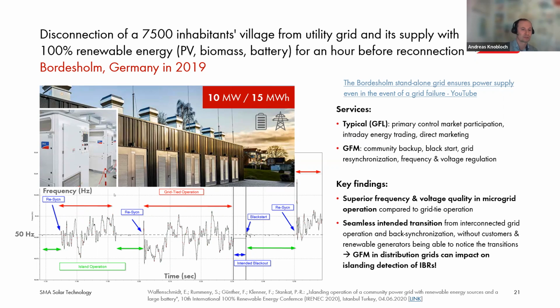So that means that grid forming in distribution grids can impact the islanding detection of inverter-based resources, and this is very important to consider for the future, because grid forming has, let's say, contradictory goals. We want to establish power grids, we don't want to shut them down. And we need to find ways to make decisions on how to deal with it in distribution grids where fast islanding detection and disconnection is required.